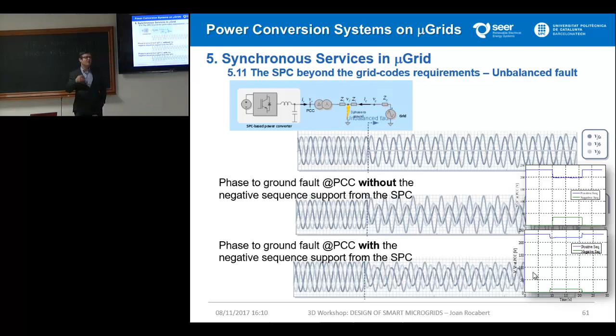If you have more converters, they will work against that negative sequence without any type of synchronization between them, without any type of high speed or low speed communication. Why? Because it is the negative sequence impedance that determines the power that each converter should give.